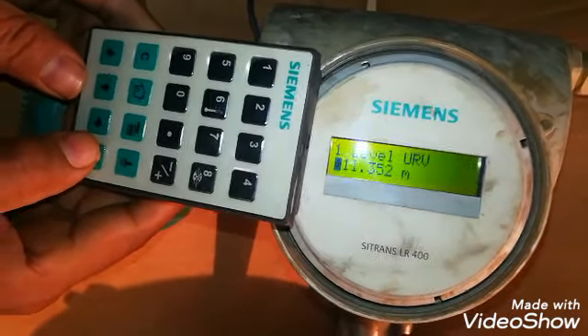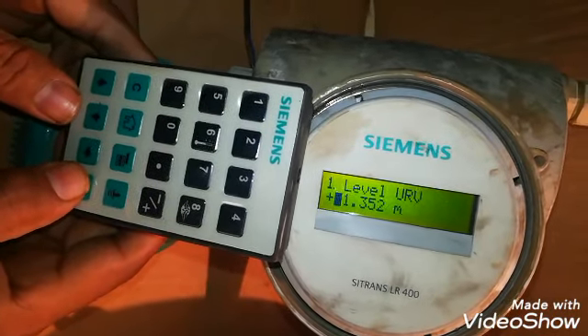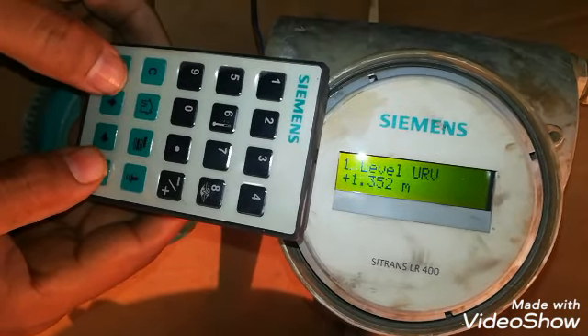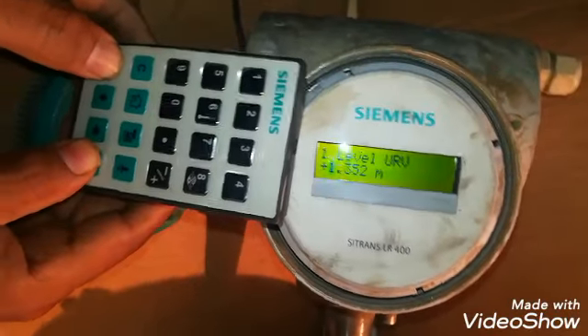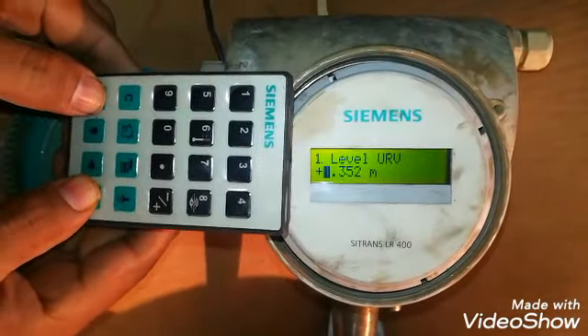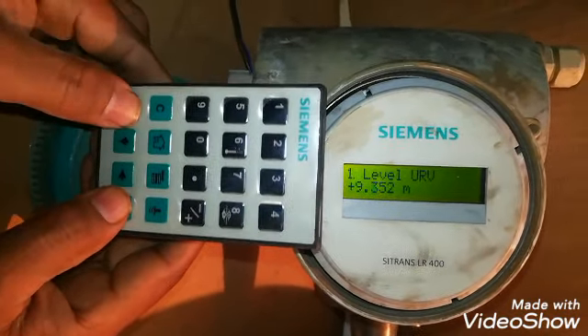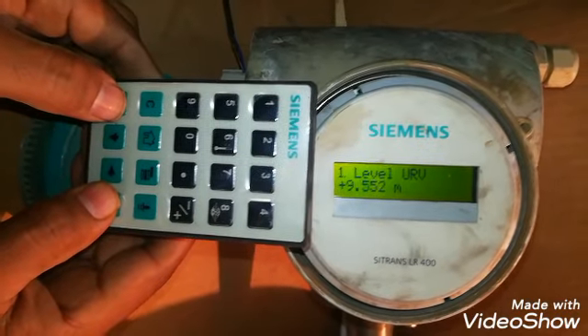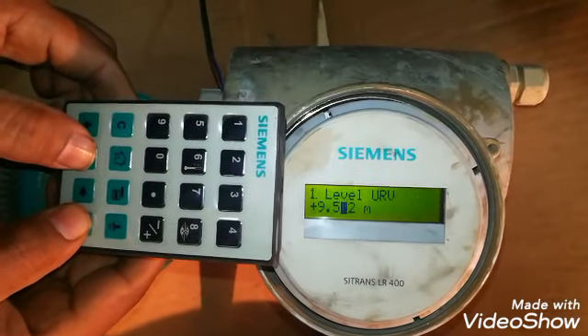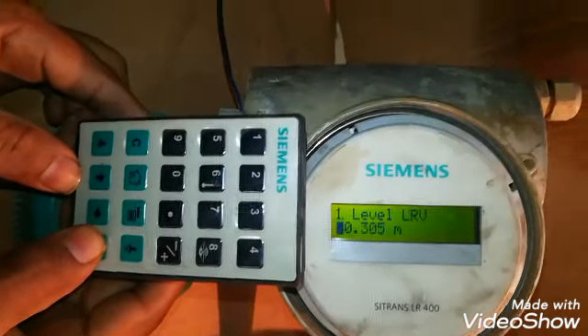URV, that at which value I want the 20 milliamps. I can change it as per our requirement, below 10 meter, 9 meter, 8 meter, where I want I can take 20 milliamps. So at that height it will show maximum level. I will make it 9.5 meters.